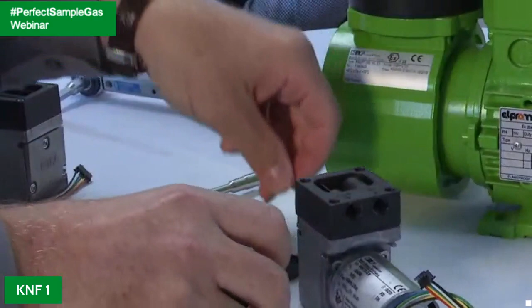Of course, the service life of the wearing parts depends on the application. If you have high pressures or highly aggressive materials, sometimes you have to change the materials more often. In a classic system, for example, if the pump runs nearly at atmospheric pressure, it will run several years sometimes. But if you ask for a thumb rule, approximately, we would recommend changing the wearing part once a year. As I said, in some applications you can run the pump much longer, sometimes it's needed to replace them at an earlier stage, but if you have the thumb rule of about 1 year, that's really good I think. Okay, great, thank you.